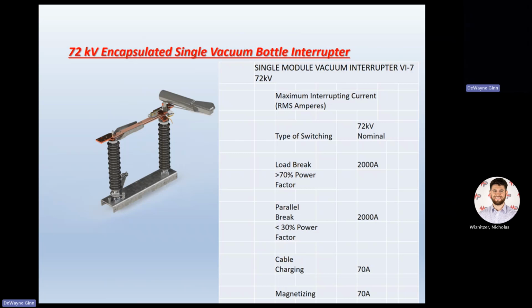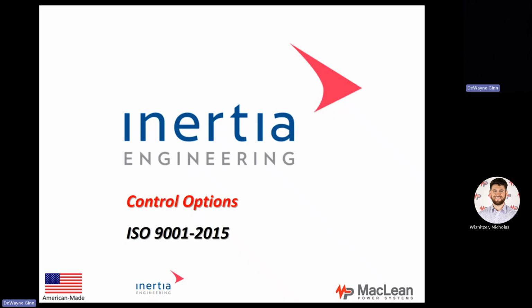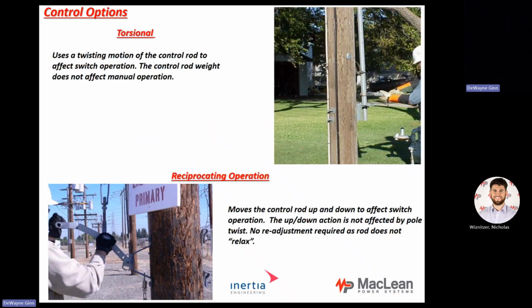Cable charge, 70 amps. On that 3-bottle setup, the best I could do would be 10 amps. So very, very much higher rated all the way around. And again, we use these on all of our 72 kV and also vacuum on our 46 or 48 kV switches. Control operation options. Again, this is the way you open and close the switch.